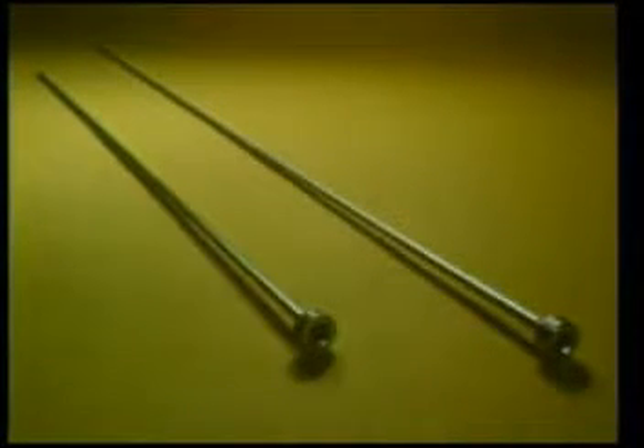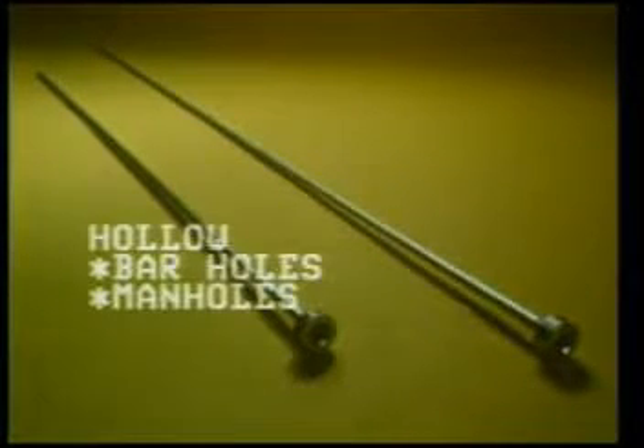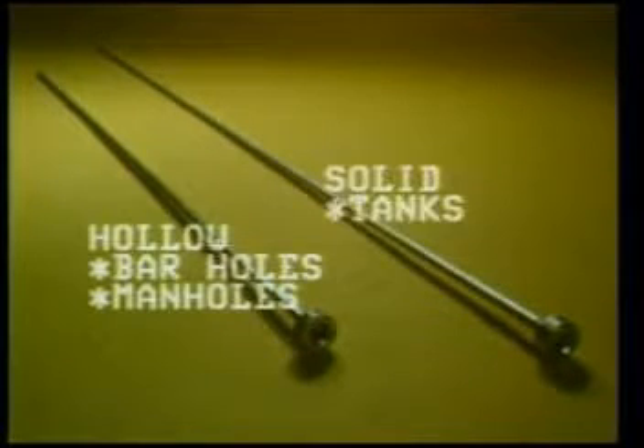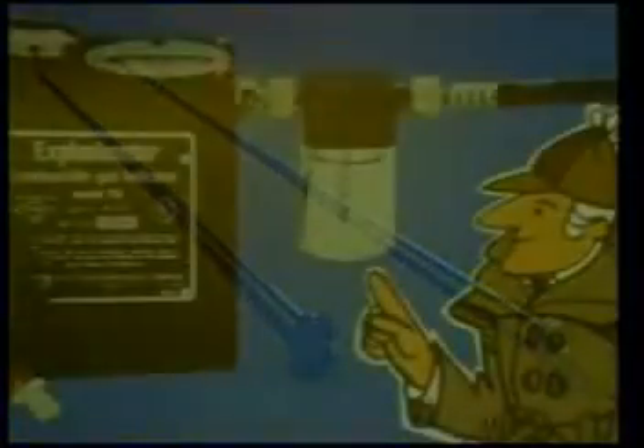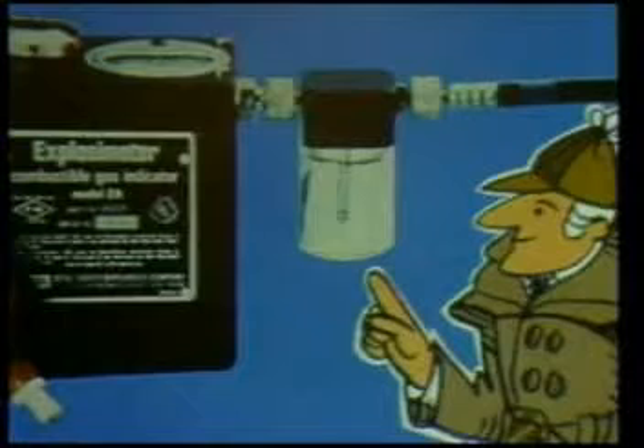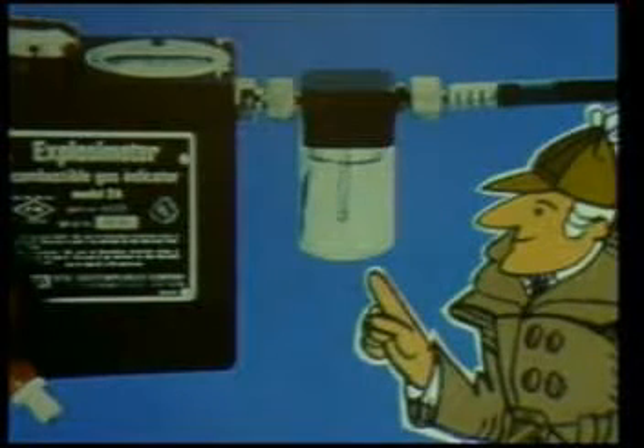Before we finish, you should be aware of several accessories for the explosimeter indicator. There's a hollow probe tube for sampling bar holes and manholes, and a solid probe rod for testing tanks that may contain liquids. When you're using probes to test in areas where conditions are unknown, a line trap like this may be used. Any liquid that's accidentally drawn into the sampling line will first appear in the bowl of the trap. Then you can stop sampling before the liquid is drawn into the instrument and causes damage.